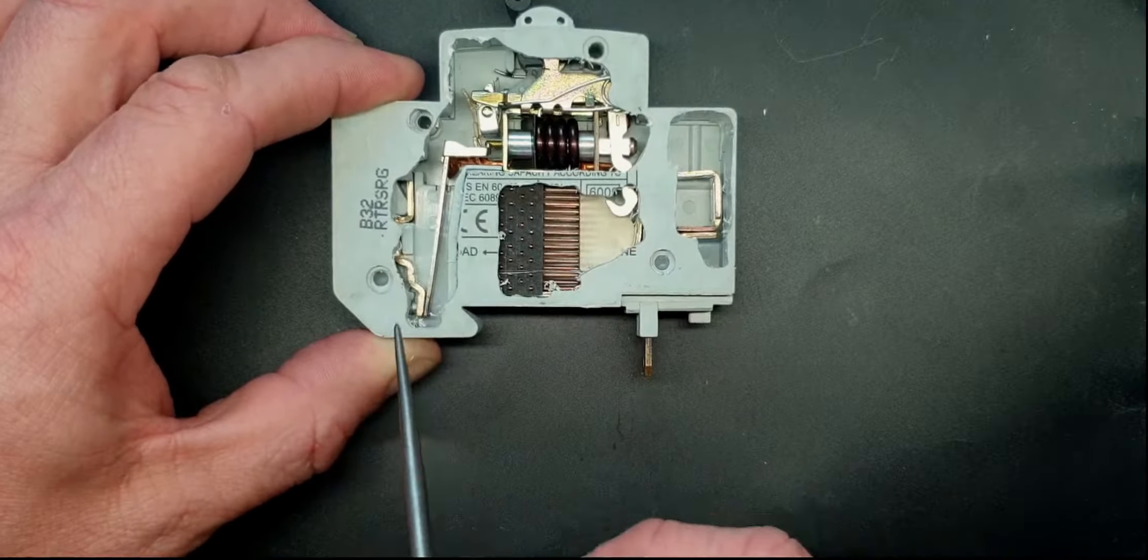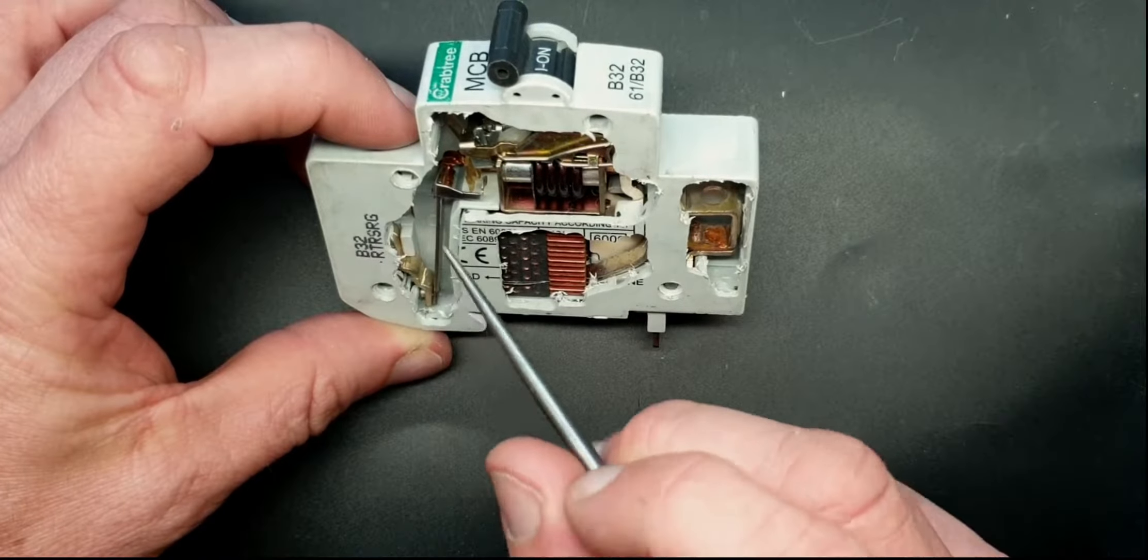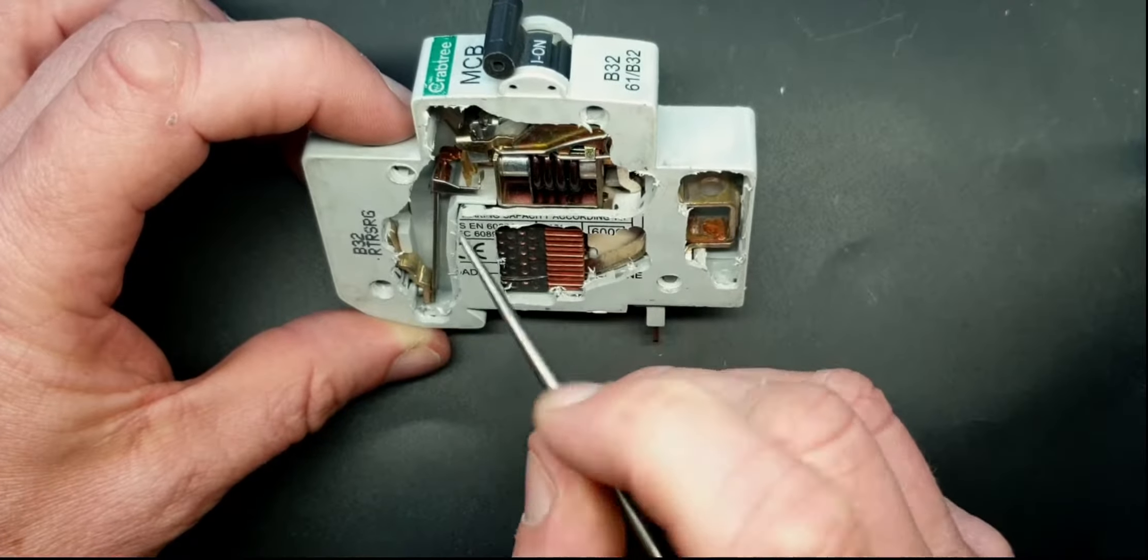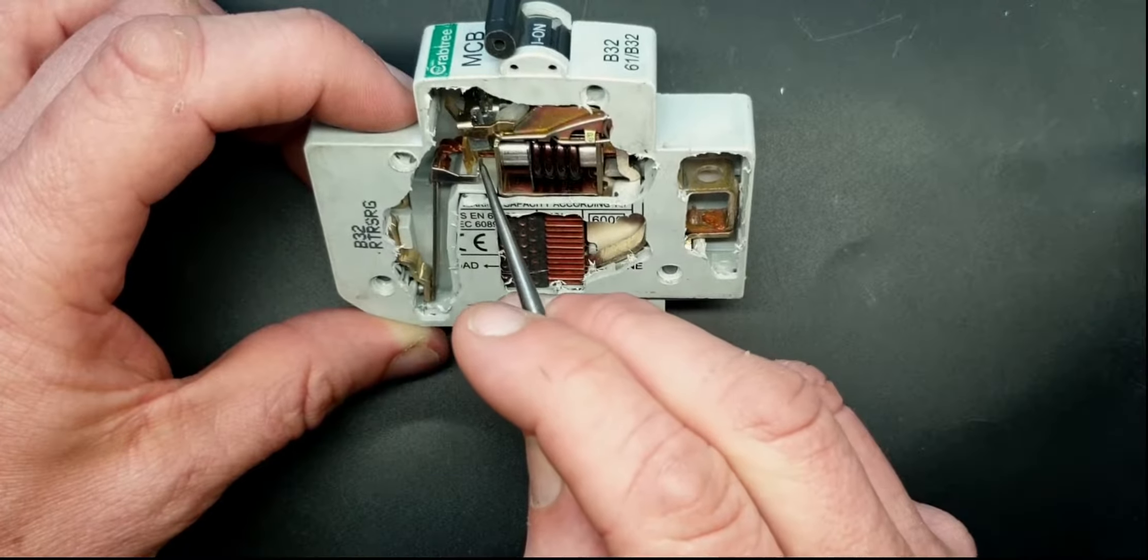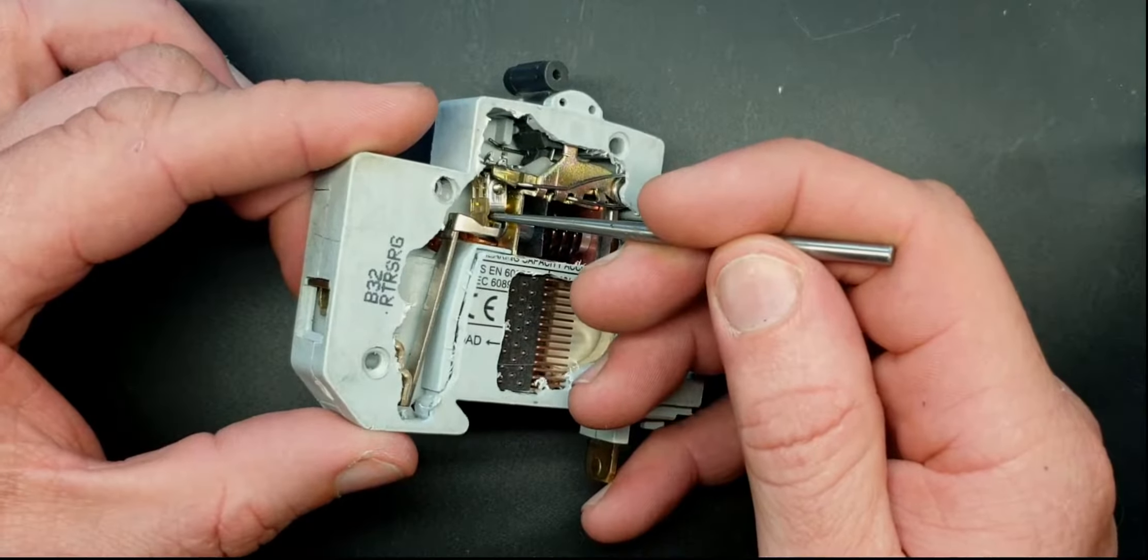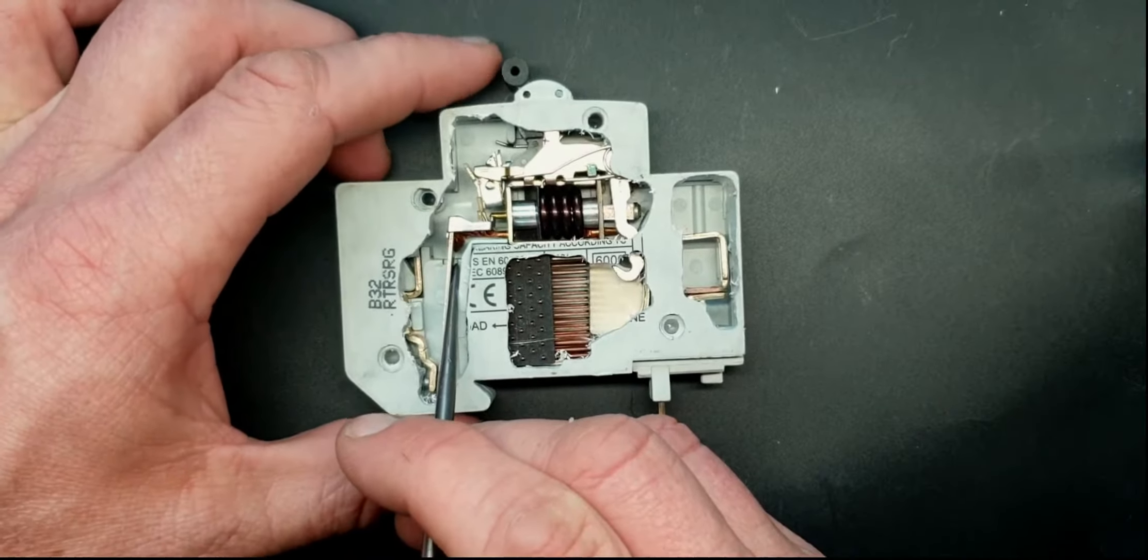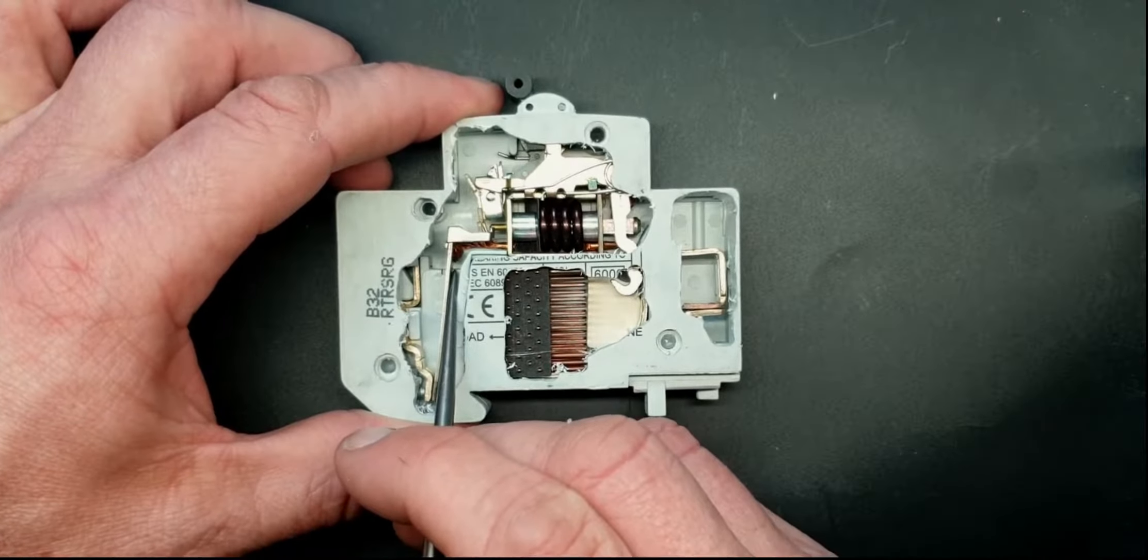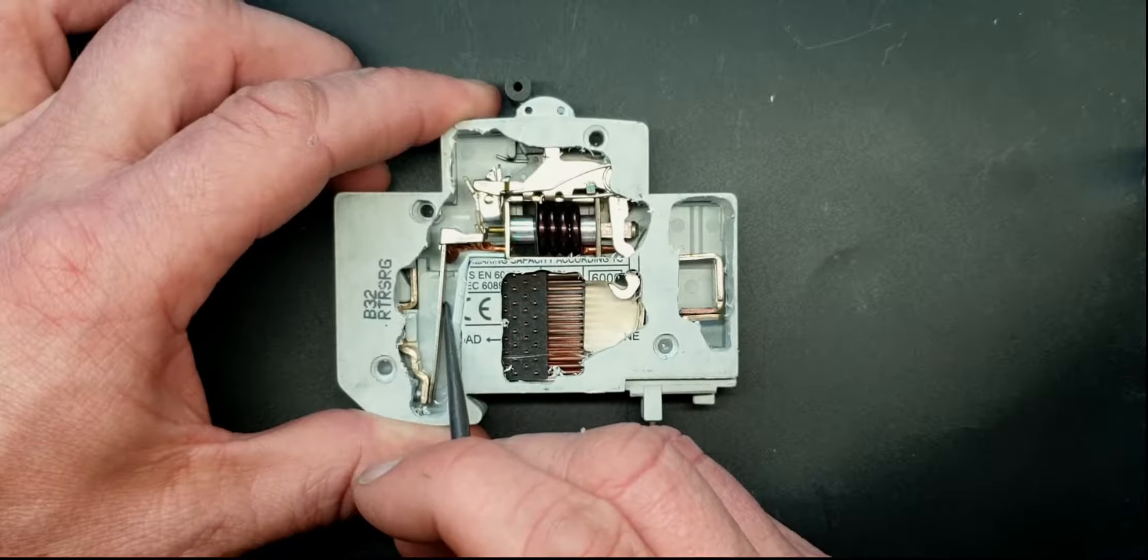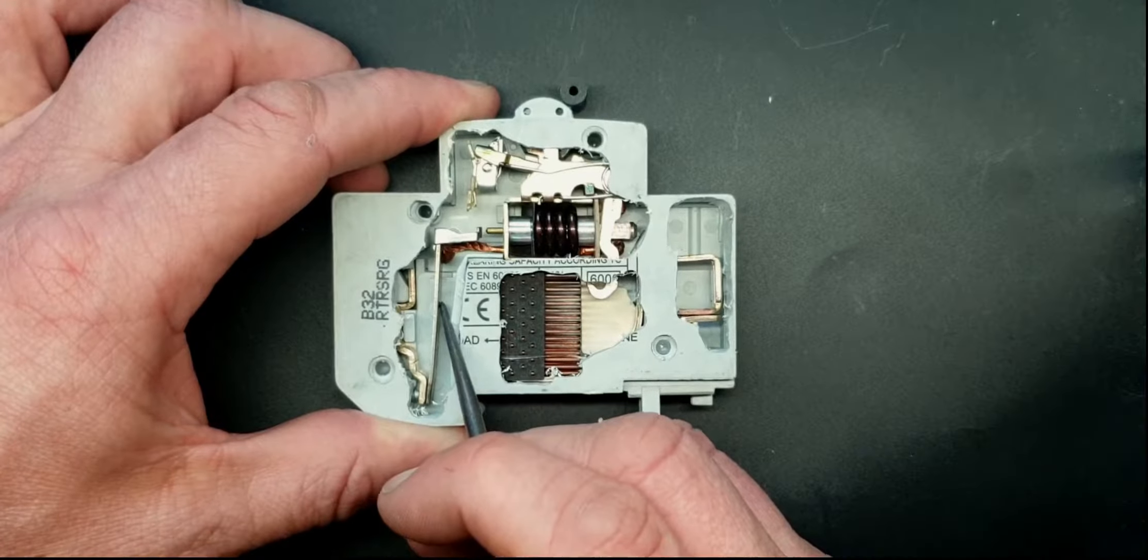You see, attached to the bimetallic strip we've got a little hook. That little hook is going to come across and it's going to hit this little plastic pressure plate just here. So as that comes across it catches that pressure plate, brings it across and switches it off.